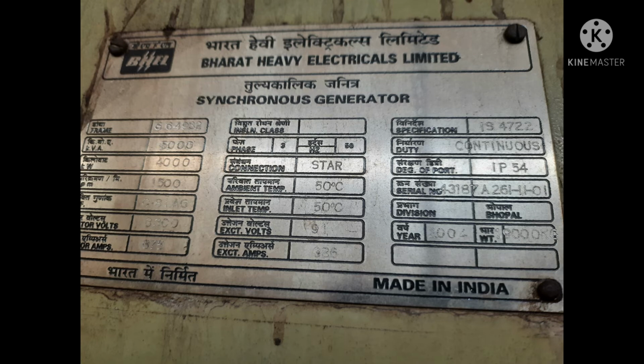After that, coming to excitation voltage, the machine has a DC excitation voltage. We give the DC excitation so that it generates 3.3 kV voltage. That is the concept of the machine. So it is written 91 volts, in terms of DC, and the excitation ampere is 336, that is DC current. It has limitations. All the parameters are given on the nameplate. They are all the limits within which the machine is running.